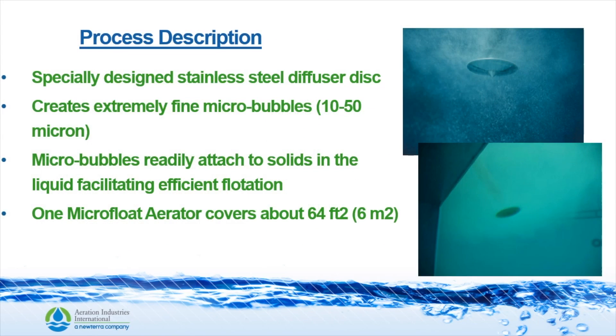The microfloat unit has a specially designed stainless steel diffuser disc. This disc creates very small micro-bubbles, 10 to 50 microns. These micro-bubbles easily attach to the fats, oil, and grease, and the solids in the wastewater and float them to the top. One microfloat unit can cover 64 square feet.